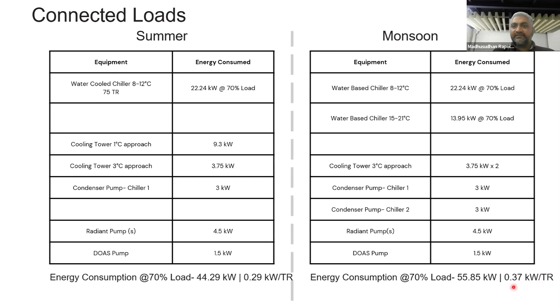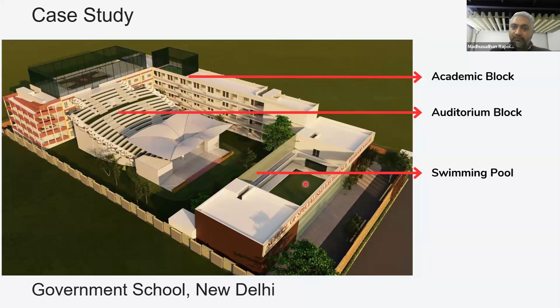A quick case study for a public infrastructure building where there is no air conditioning or very little vapor compression based system. This is an upcoming building in Delhi, right next to the T1 terminal. This is the school, and this is the piping embedded in it, and the swimming pool here acts as the heat sink and provides a warm pool. Please understand that the pool will not get hot because you are only removing heat that is marginally increasing the temperature. So let's say you start this from the end of Feb, you would never be removing heat that has reached 40 degrees centigrade in the structure. You keep this building structure temperature always at 30 degrees centigrade. So the pool remains at about 26, 27 degrees centigrade always, and due to night sky radiation, it cools down.